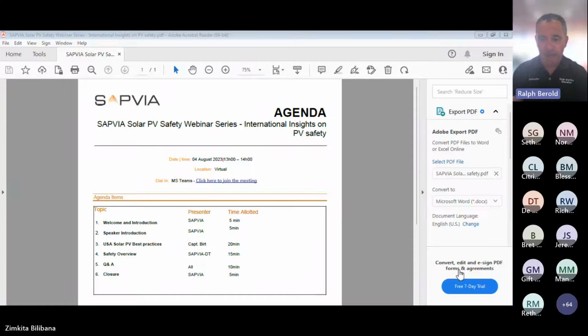And rapid shutdown means when there is a problem on the roof, how do you shut that system down? If you have a string inverter with no rapid shutdown or no way to shut it off, when the sun is shining, you create an arc fault, and that voltage from the roof that you can't shut down is feeding that arc. And it continues to burn. The roof structure could be tile, but you're talking about temperatures of 4,000 degrees Fahrenheit and above. What you're looking at is you're catching other stuff on fire. You're catching roof members. You're catching wood that is underneath the shingles or underneath the tiles. So we said, how do we do this? How do we stop these houses from catching on fire or commercial buildings? And we said, okay, rapid shutdown would be critical, where we can shut down the main power and it shuts down the system. Well, we got to rapid shutdown, but we still had high voltage DC.